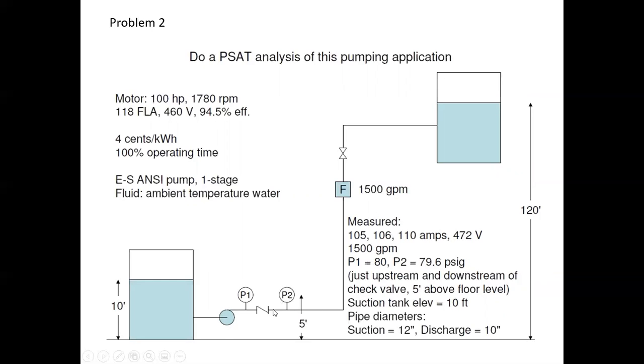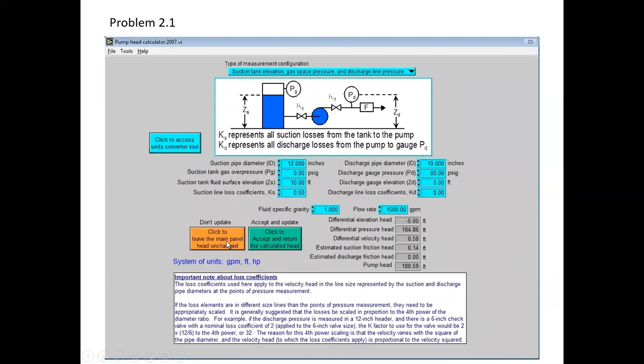Okay, so we look over here at the diagram. So we got a discharge gauge on the pump at P1. We've got a check valve, and we've got a P2 that's measured just on the downstream side of the check valve. All the gauges are 5 feet elevation. In pipe diameters, I got 12 on the suction and 10 on the discharge. And all this stuff is at 10 inches on the discharge side of the pump. There's our flow meter. Okay. So we're going to have to do a PSAT analysis. So we know we're going to have to calculate pump head.